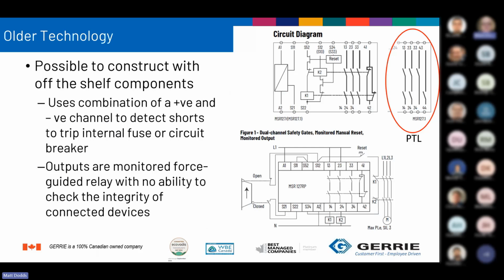With older technology, it was simply, again, like 3 relays in a box. You could have 2 positive channels. You could have 1 positive and 1 negative channel, and they used like an internal fuse or a circuit breaker or self-resetting fuse. So if I took S11 and shorted it to ground, or that channel going from S11 to S12 to ground, it would simply trip out that internal fuse or breaker and then drop the relay. However, if I shorted it to positive, it wouldn't do anything because it doesn't know, which is again the advantage of using pulse test inputs.